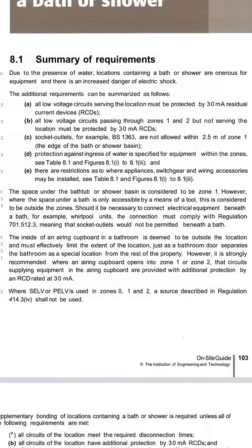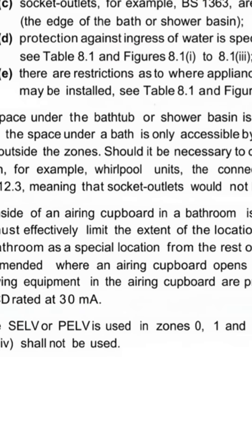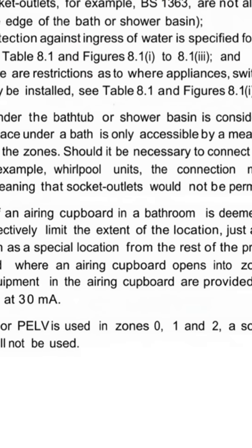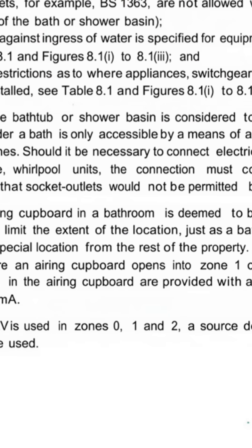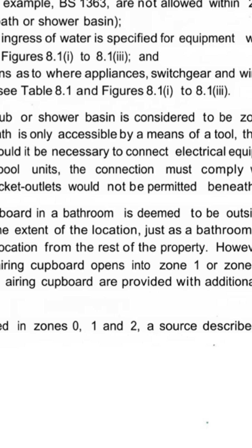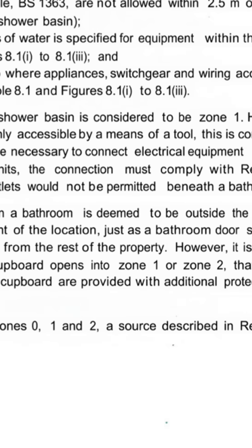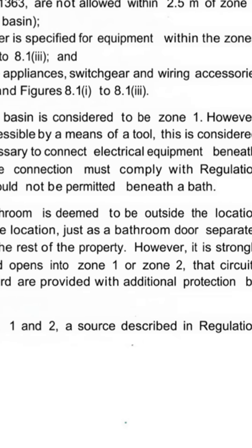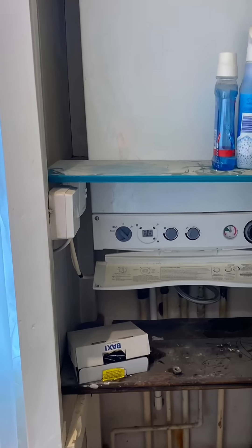What is actually recommended in the on-site guide is that 30mA RCD protection, as additional protection, is used for the circuits serving the inside of the airing cupboard.